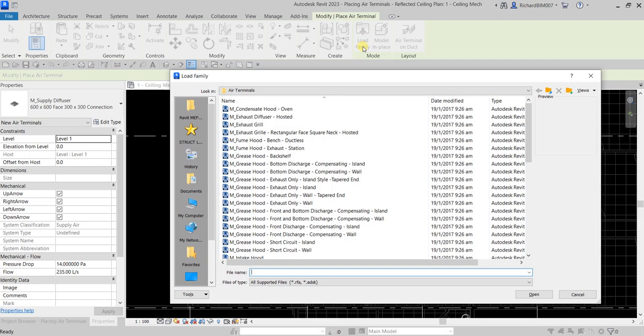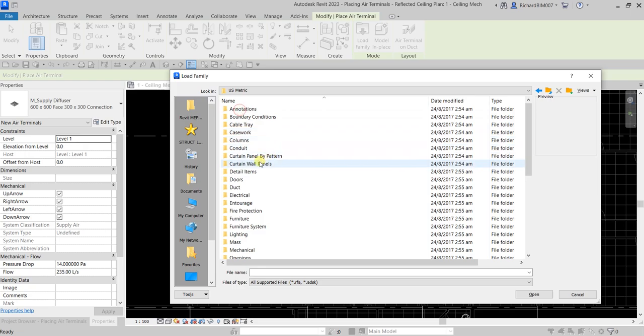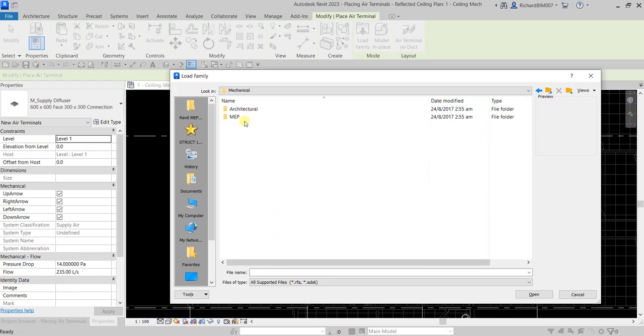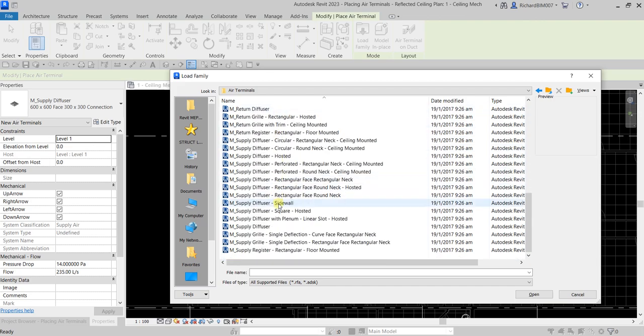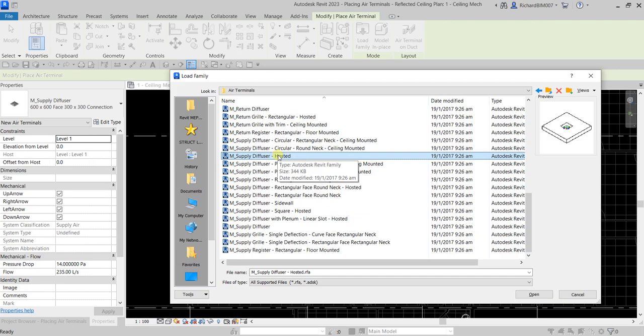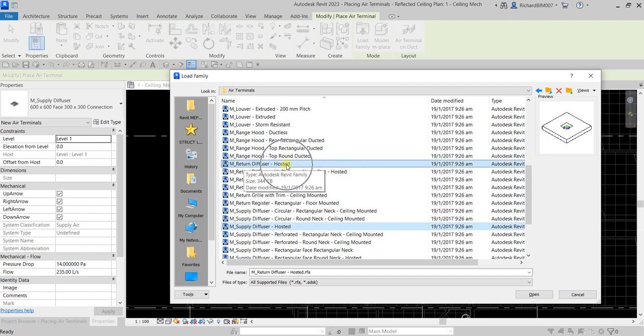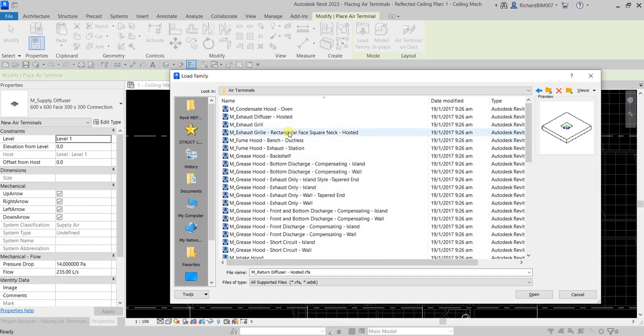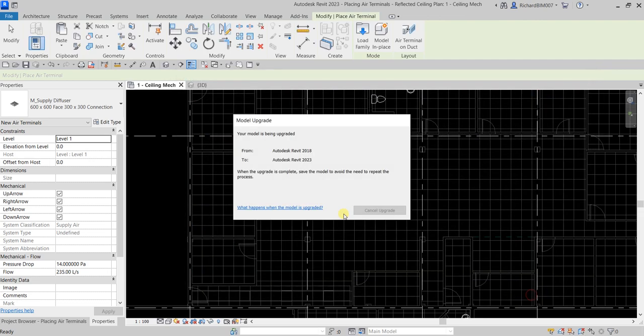If you have an air terminal saved in your project or folder, select Load Family and navigate to the air terminal folder. I'm using the Revit 2018 library — go to Libraries, US Metric, then Mechanical, MEP Air Side Components, and Air Terminals. I'll load the M Supply Diffuser Hosted, Return Diffuser Hosted, and Exhaust Diffuser Hosted — hold Ctrl to select multiple families, then click Open. Revit will upgrade them from 2018 to 2023.